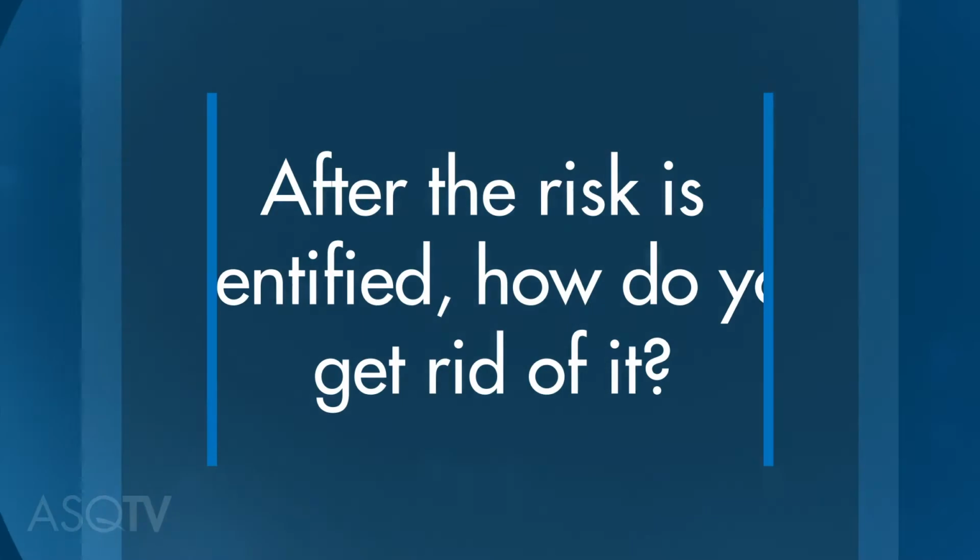And the final source of risk is, you can do all that right, and if the customer doesn't use it as intended or maintain it as intended, your product's going to fail. The tool we use is what we call a usage risk assessment. Some people call it a process FMEA on the use of the product. Other people call it an application FMEA. But the bottom line, what we're trying to do is anticipate every possible user misuse and make sure either we have the elements in our design to react to it or we've provided adequate instructions.